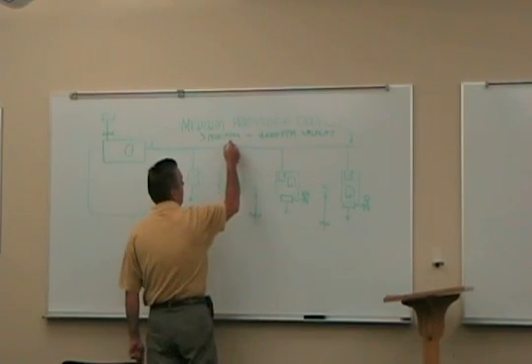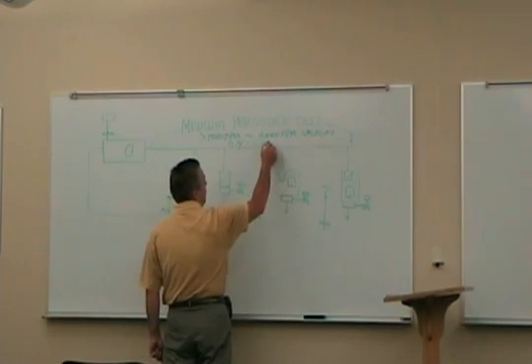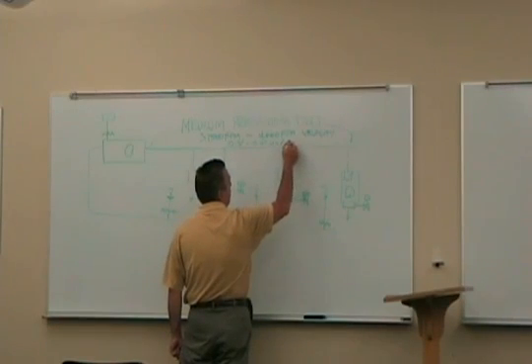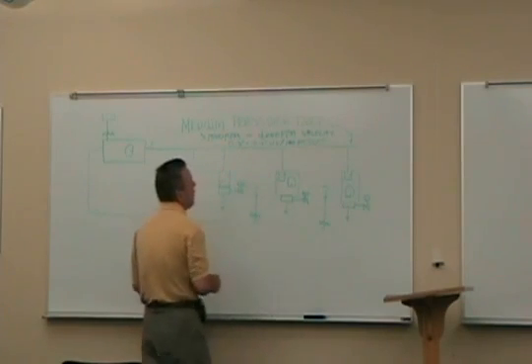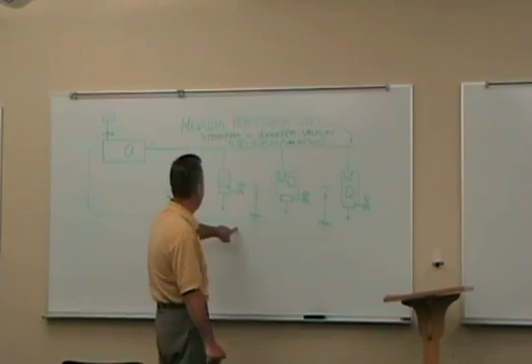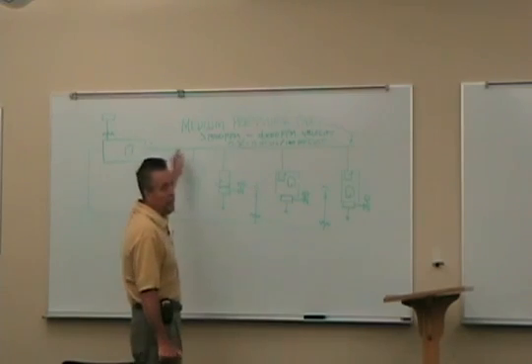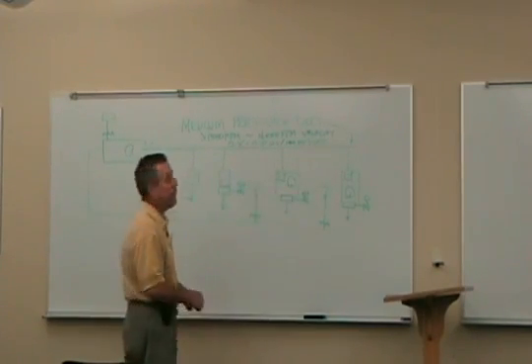And probably ranges 0.3 inches to 0.4 inches water gauge per 100 feet of duct. There's different ways to size this kind of duct. The reason you have these high velocities in relation to velocities here, which we'll talk about, is that that duct just gets too big to fit in space.